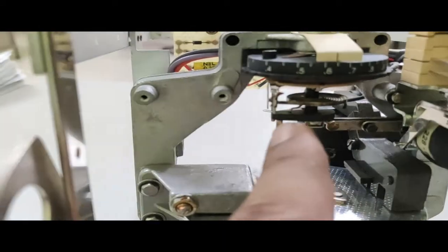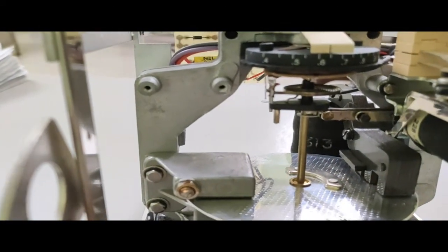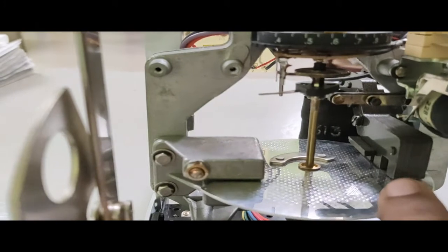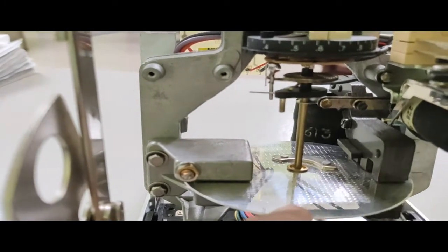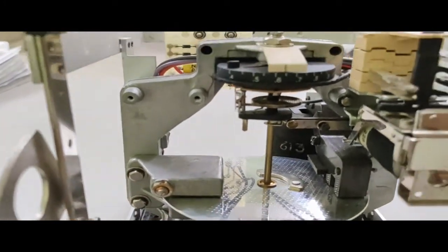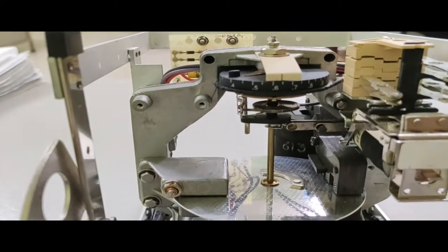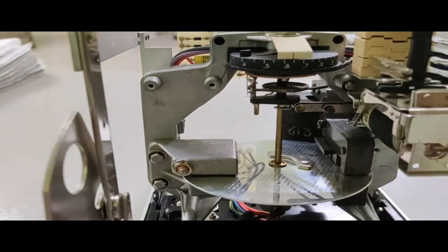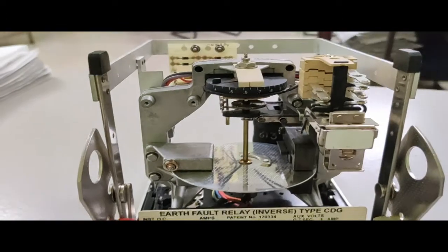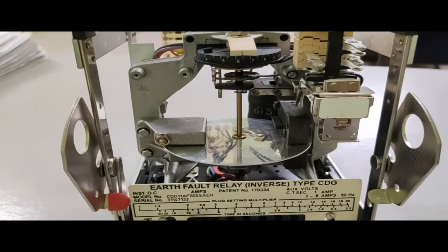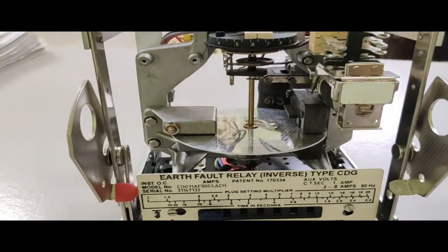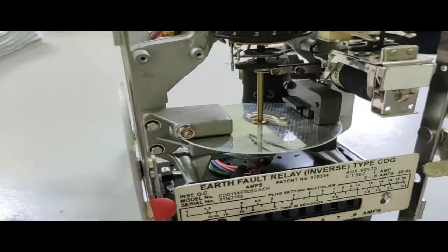So these are the spring sections. Some spiral springs are there because, after the relay operation, when the actuating force is not present, the spring ensures that the disc comes back to the initial position. So this is the construction of the electromechanical type relay, and this is the induction relay because the disc is rotating due to induction.